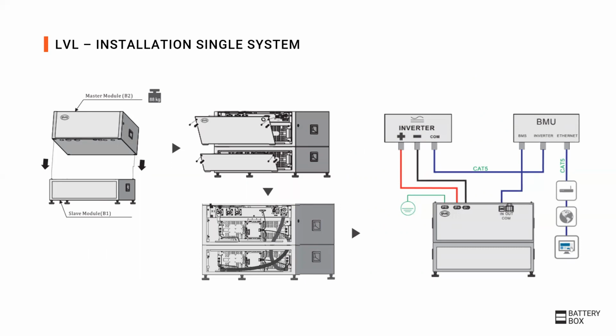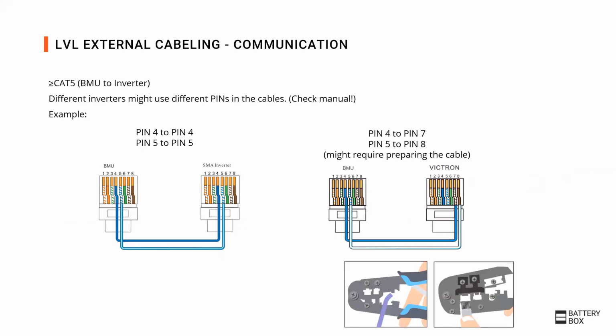The communication cable from the LVL goes to the BMU and from the BMU to the inverter as shown here on the right side. Make sure that you use a Cat5 or higher cable for the communication connection with the inverter. Also, some inverters might require a special communication cable like shown here on the right side. Please check the manual for the correct cabling.